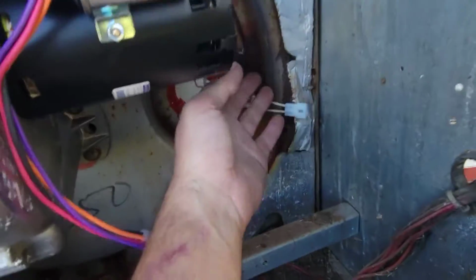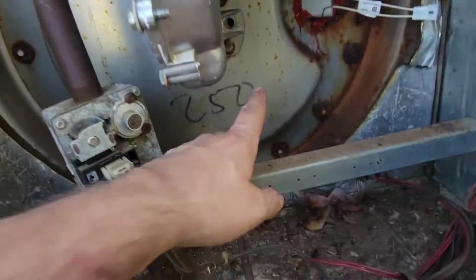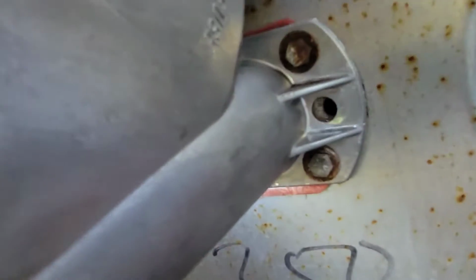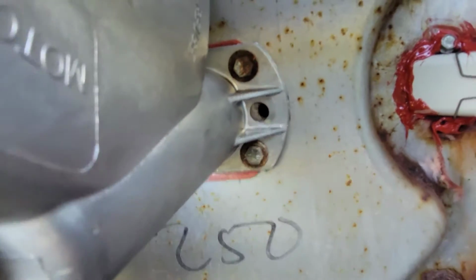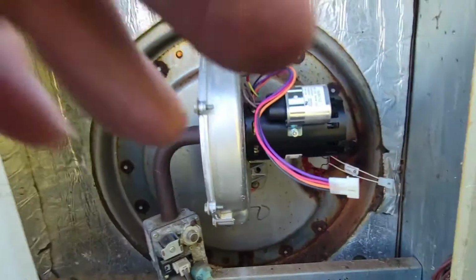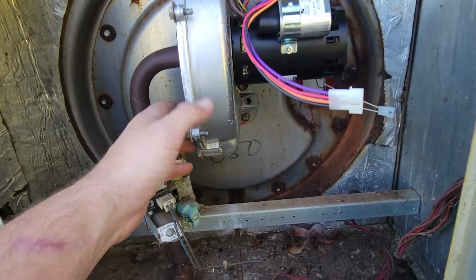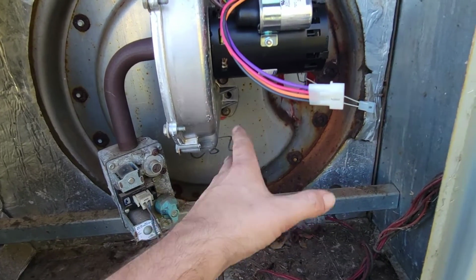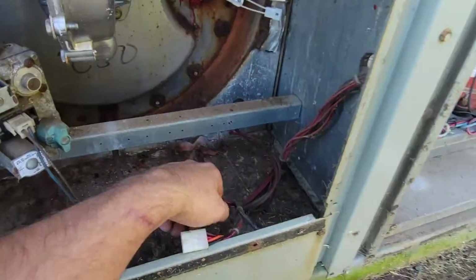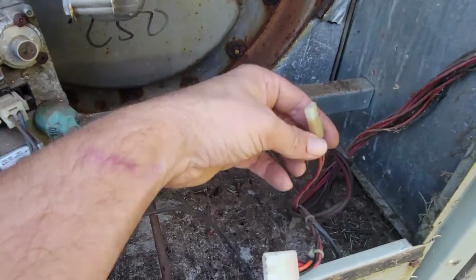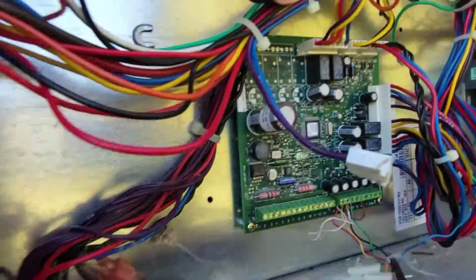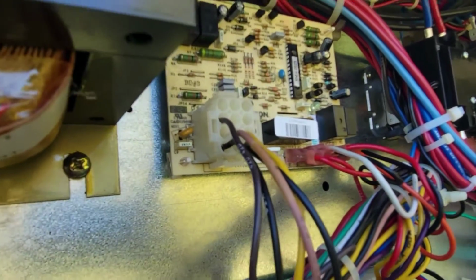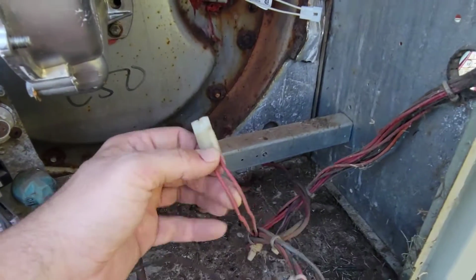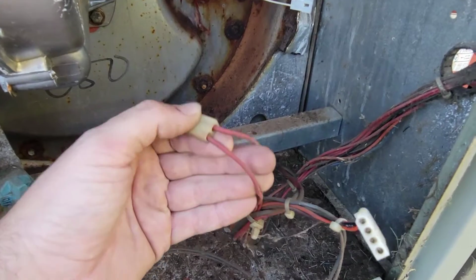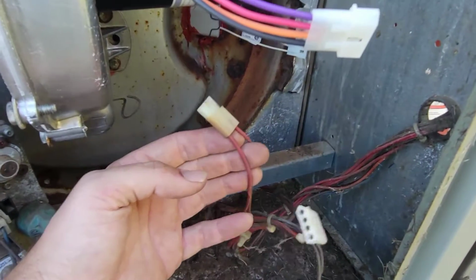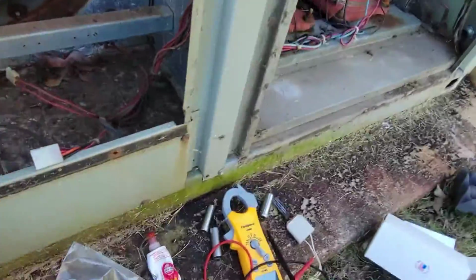I got power to my hot surface igniter, but it didn't actually glow. I could tell it wasn't glowing because there's a little sight glass in here where you can see inside the actual chamber where you have your flame created, where you have your hot surface igniter glowing. So I couldn't see it glowing, and I had 120 volts, and this right here is the plug that comes from the ignition control board, right there, ignition control board. This right here is the plug that goes to the hot surface igniter, and I checked across the plug and there was 120 volts. Now I'm going to show you 120 volts and show you the bad hot surface igniter.